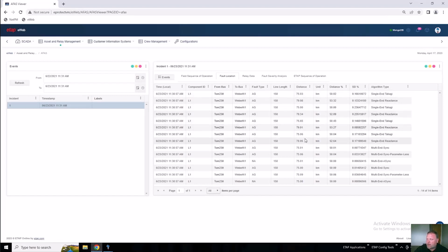The distance. Now you can see here that you have various different values for the distances. And this is because each algorithm has its own strengths and weaknesses. So for instance here, the single-ended Takagi provides 75.03 as the distance in kilometers away from the TOM 230 bus, whereas the single-ended reactance gives me 79.93 kilometers away.